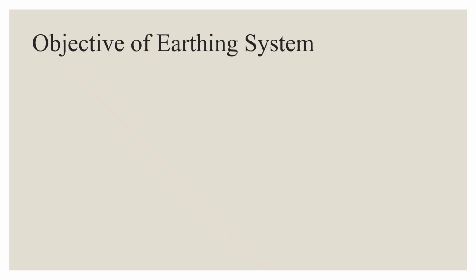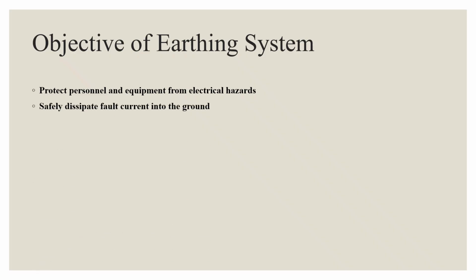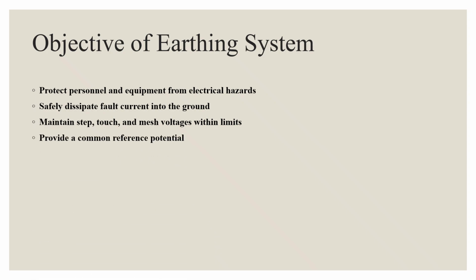So the main objectives of an earthing system are, first, to protect both people and equipment from electrical hazards. Second, to safely dissipate fault currents into the earth to prevent dangerous potential differences. It also ensures that step, touch, and mesh voltages remain within tolerable limits and provides a common reference potential for all electrical systems. In short, earthing ensures that any fault current flows through a low resistance path instead of through human bodies or equipment.